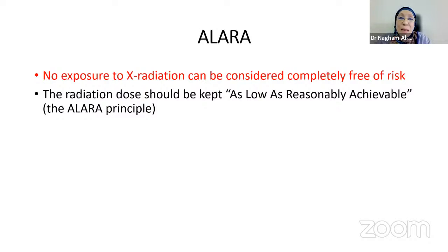I want to introduce another concept for you, the ALARA concept or the ALARA Principle. No exposure to X-ray or X-radiation can be considered completely free of risk. For this reason, it is recommended that the radiation dose should always be kept as low as reasonably achievable, which is the ALARA Principle, the abbreviation of this principle. And this principle, you will see it in all radiation regulation worldwide.